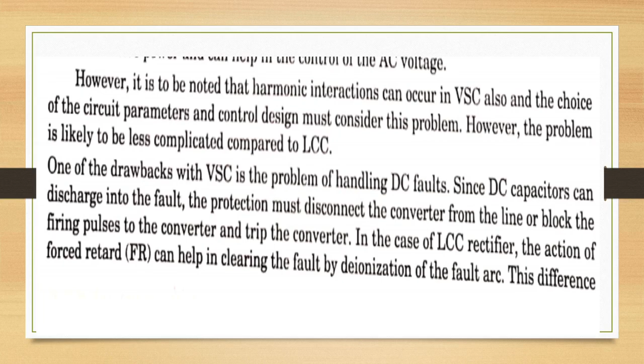One of the drawbacks with VSC is the problem of handling DC faults. Since DC capacitors can discharge into the fault, protection must disconnect the converter from the line or block the firing pulses to the converter and trip the converter. In case of LCC rectifier, action of forced retard can help in clearing the fault by deionization of the fault arc.